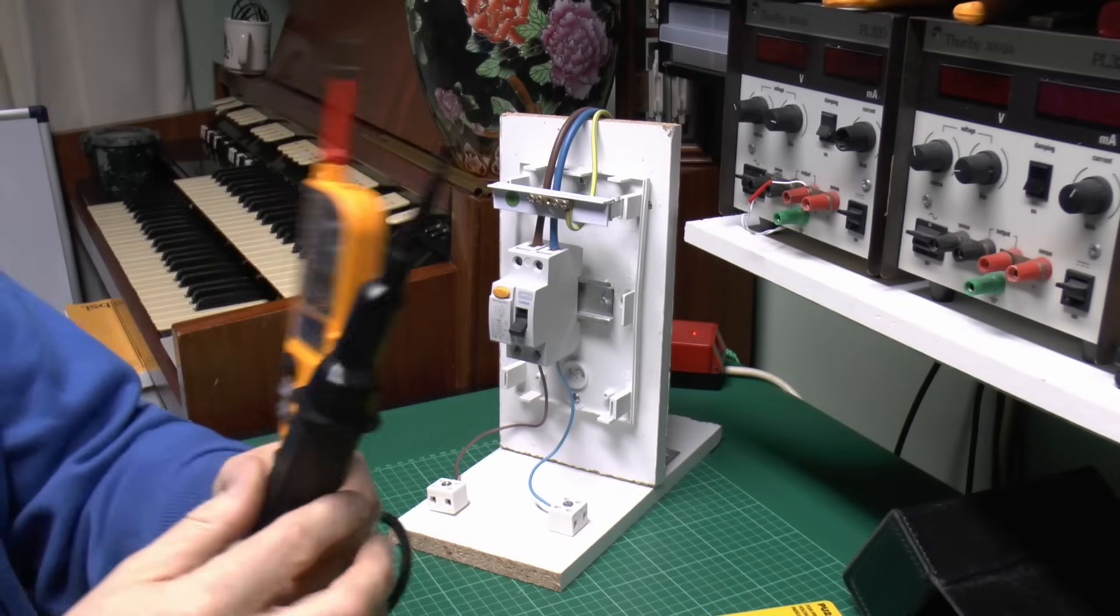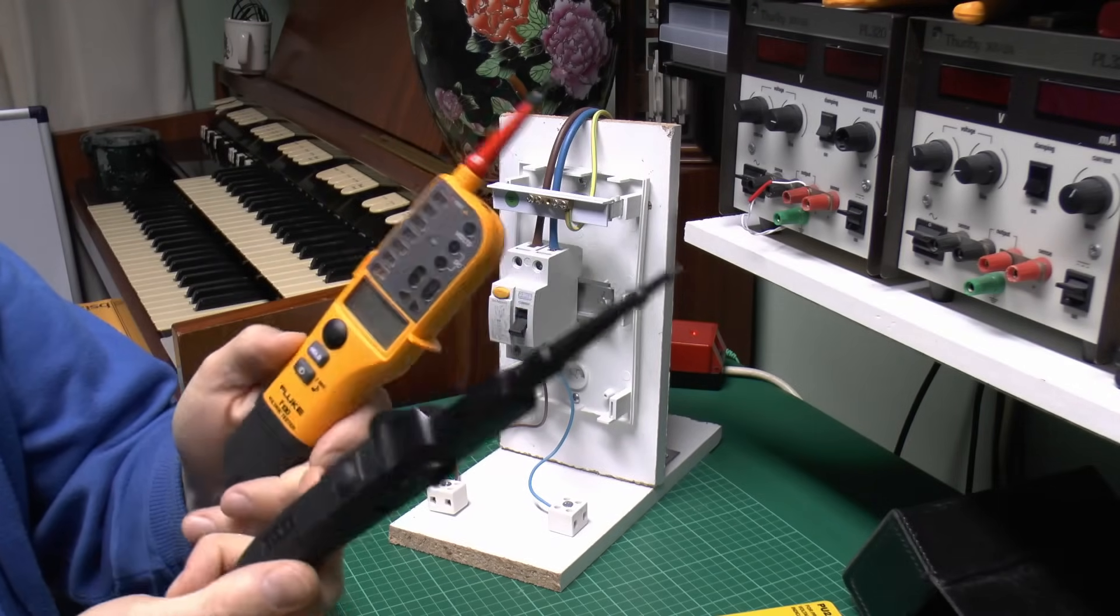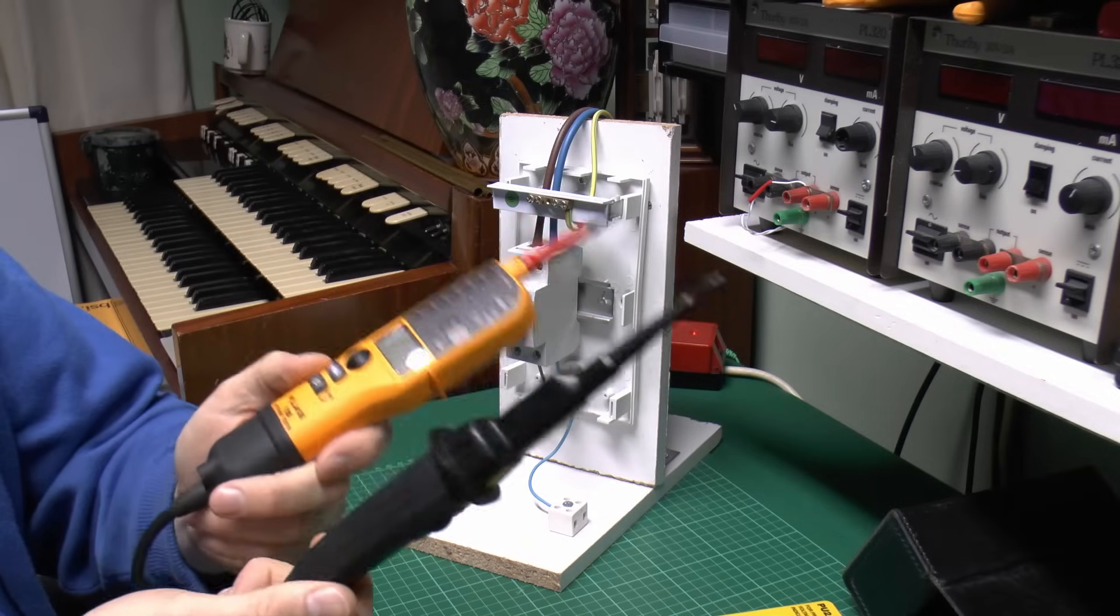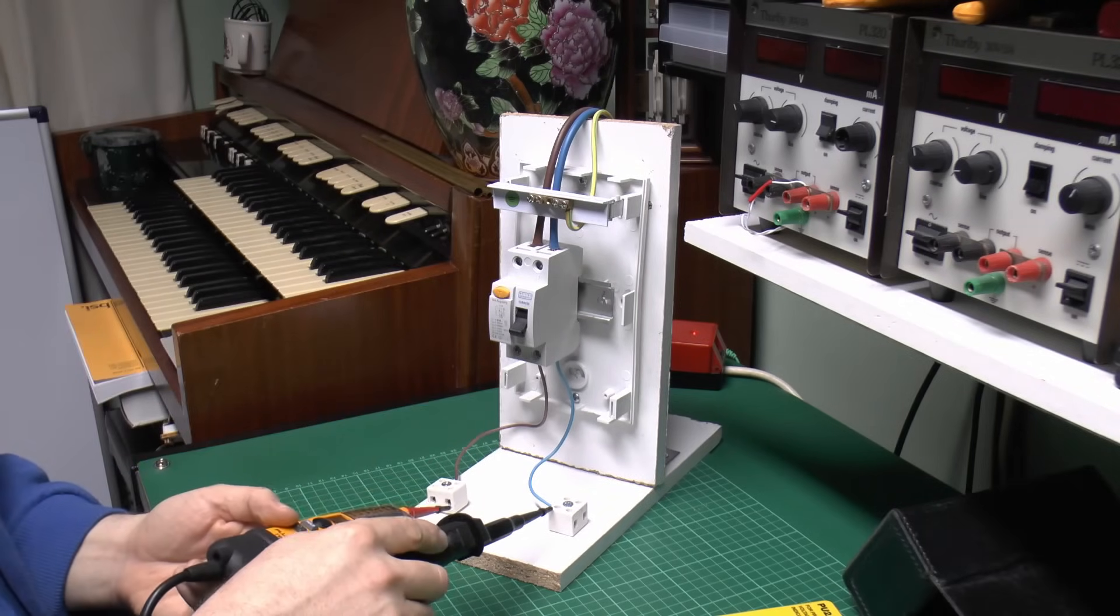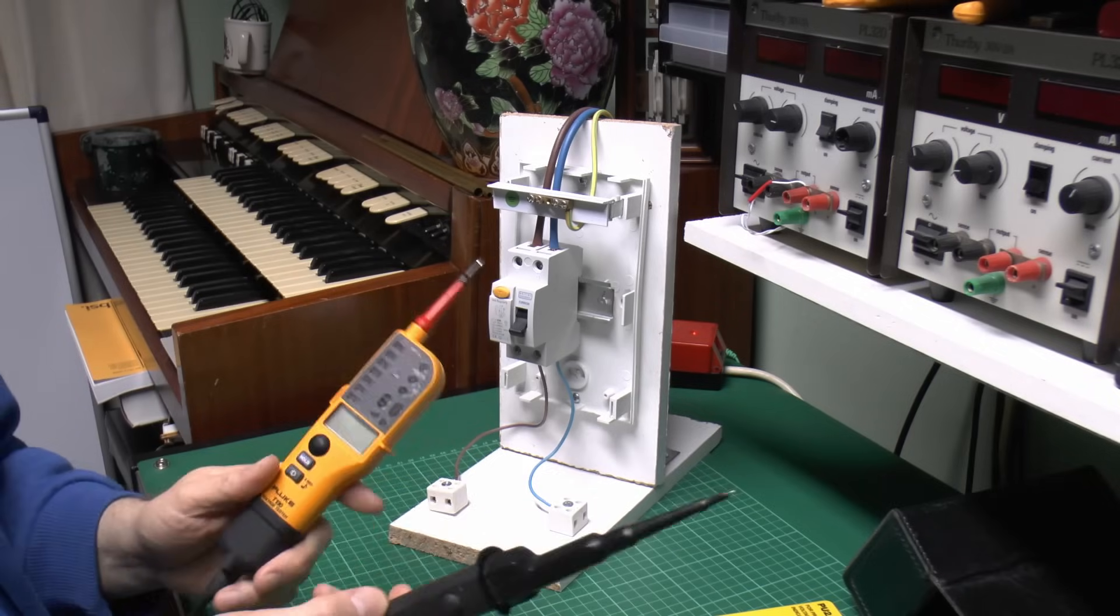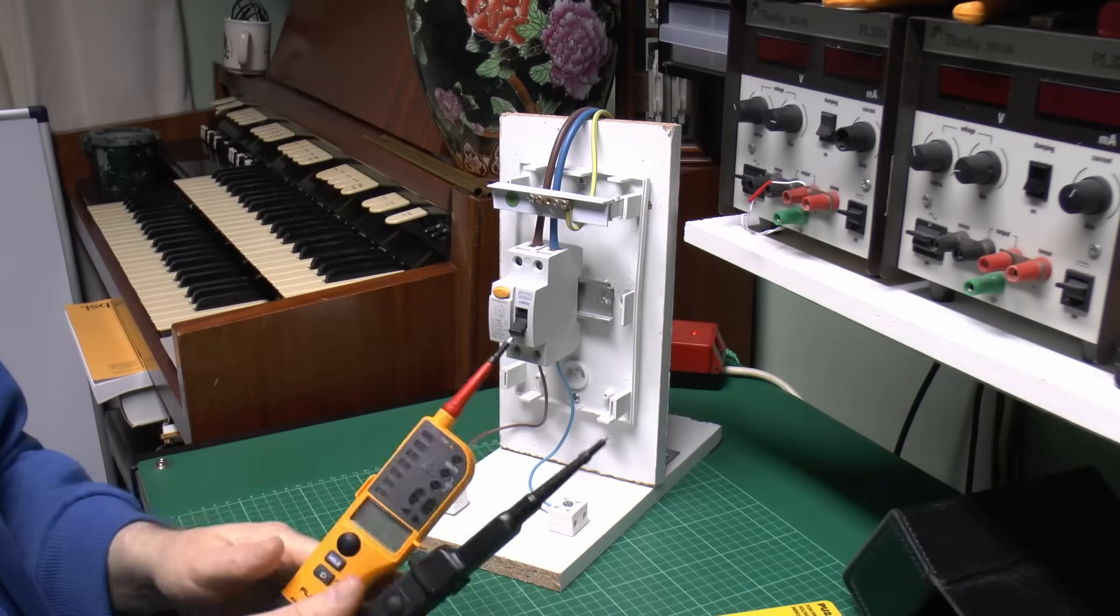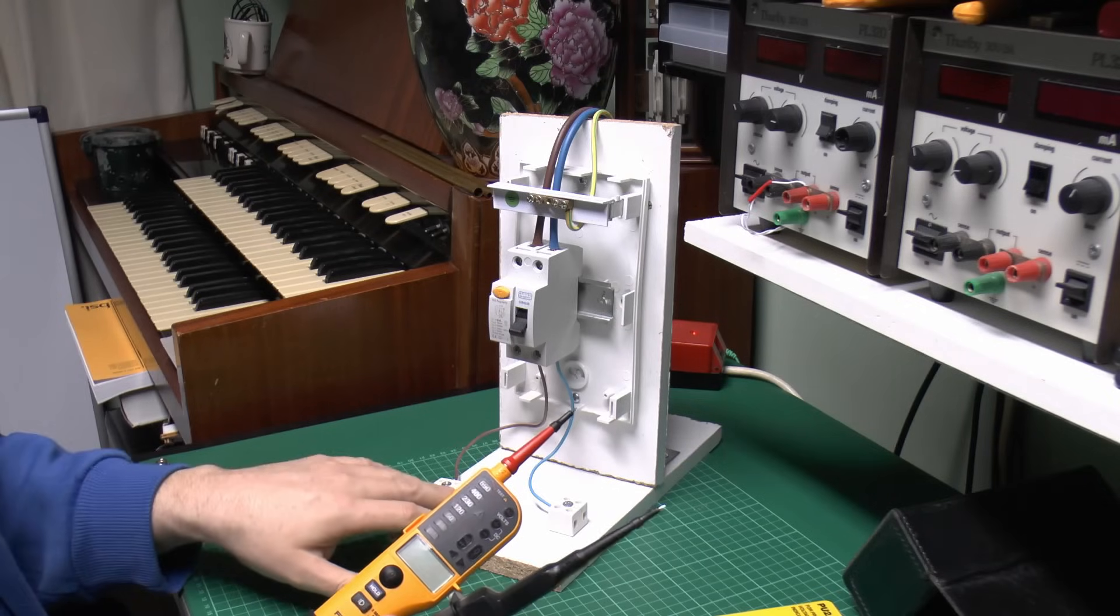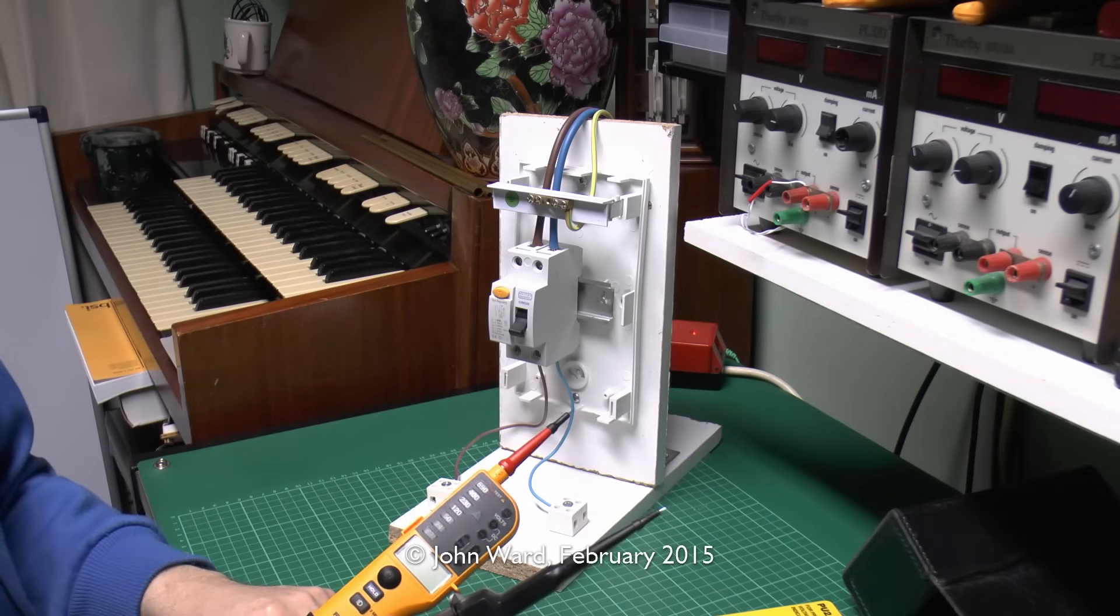So in summary then it's a proper approved two-pole testing device, check that it's working before use, then check the circuit you're going to be putting your fingers on, and after that check again that it's still working, and then you've got a good level of confidence that the terminals here are in fact disconnected and therefore safe to work on.